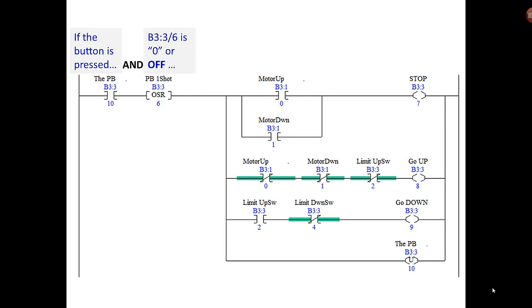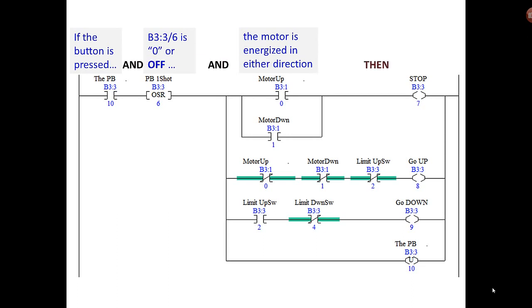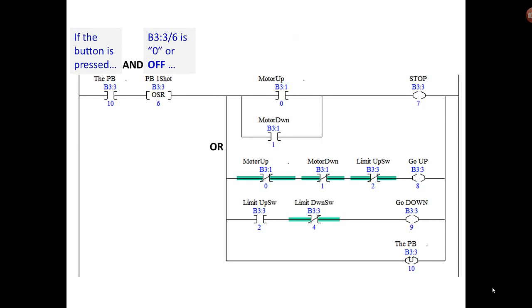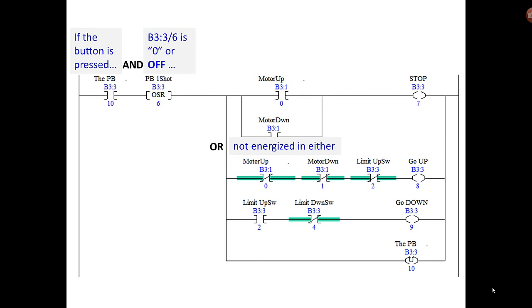It'll set the instruction true and then it'll move on into the rung. So this one-shot is only going to be true when it's discovered for that bit to be off. It's going to set that bit on and be true, and the motor is energized in either direction. So if the motor is running in either direction, then set the stop bit. Or if you push the button and B3:3/6 is off, meaning it hasn't been visited with the left side true—which is the push button—it can set the stop bit.